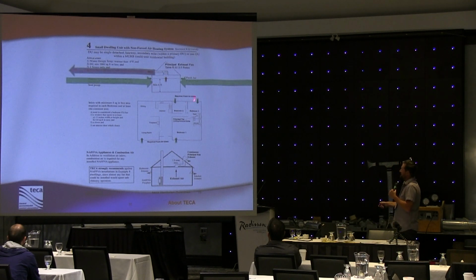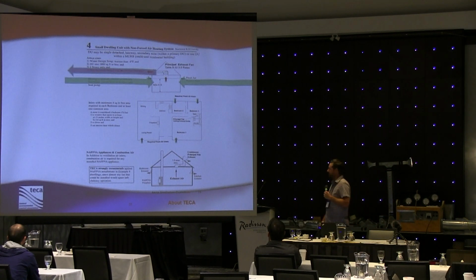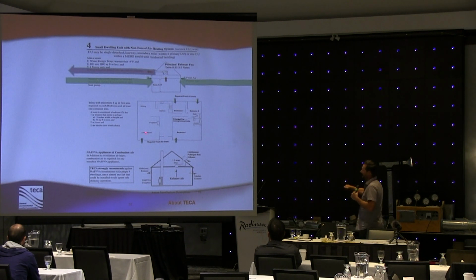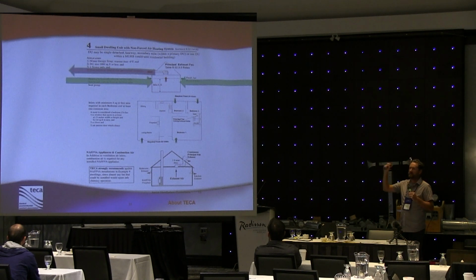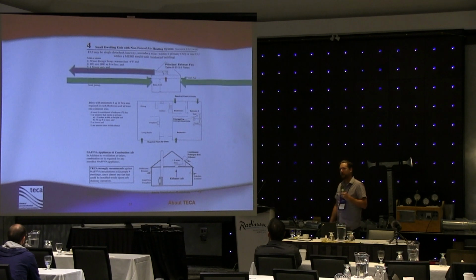The way they work is that we have a principal exhaust fan, typically a bathroom fan, that is going to be exhausting 24 hours a day. The way that fresh air makes its way back into these bedrooms, if you look here on this little floor plan that I have here, the way that fresh air makes it back into these bedrooms and back into the common area is just with a single opening right through the building envelope. There's no fan bringing this air back in, there's no ductwork attached to it.